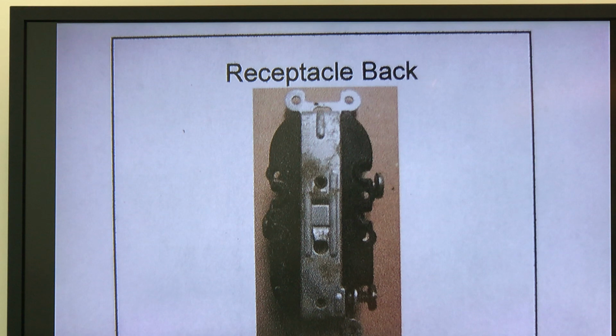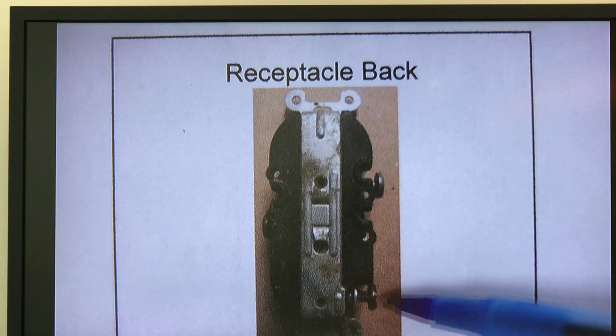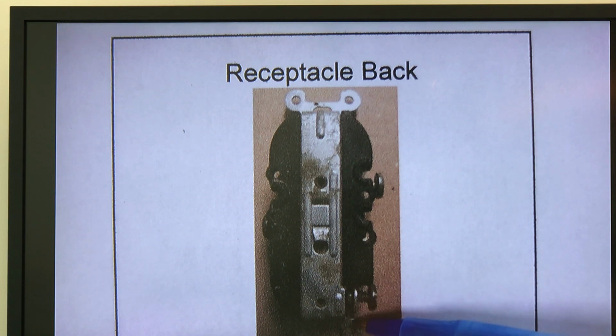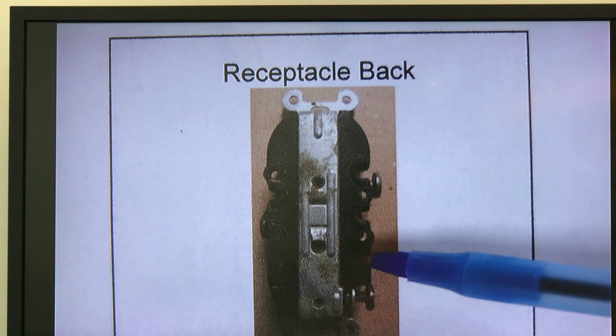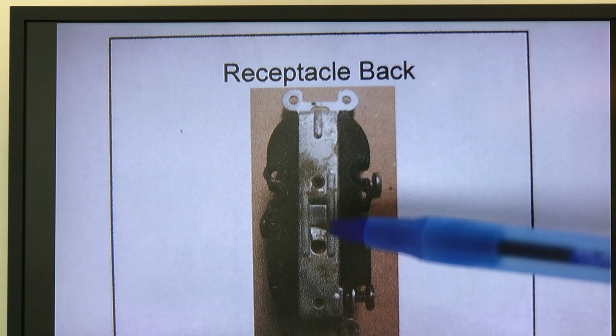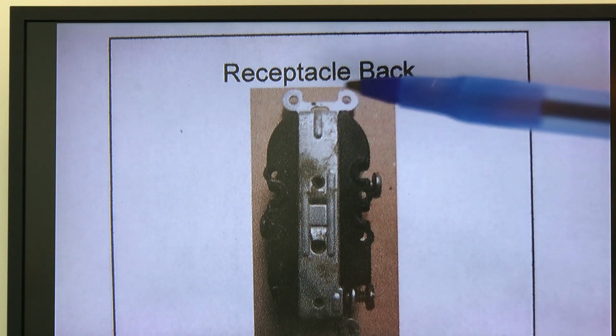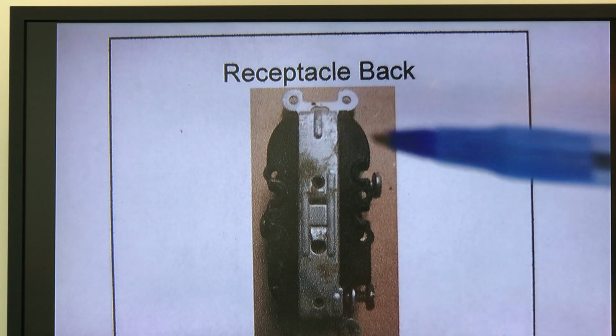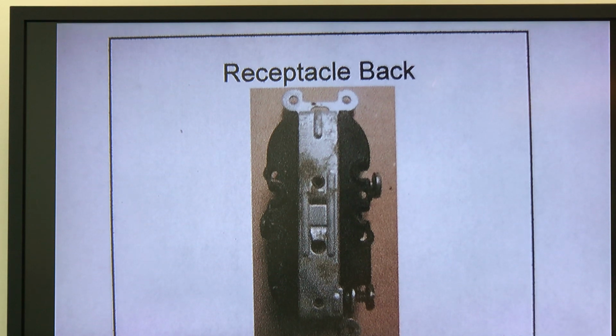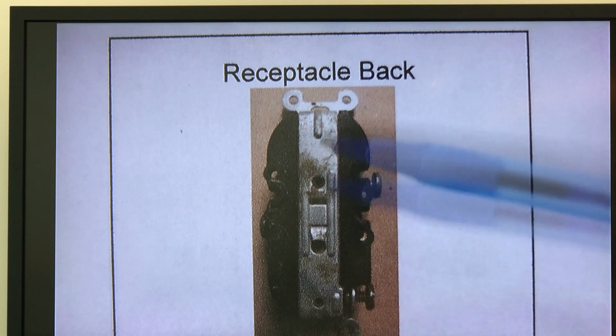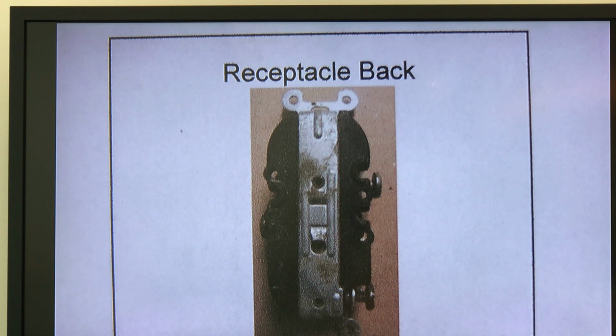If you take a look at the back of the receptacle, and this is the same device, and it was one that was pulled from service, because they do get a little grungy. You're looking at the back, and down here I want you to notice that here is a screw. That's for the ground connection. That ground connection is established to the little piece of metal here, which is actually an extension of this entire back strap. And then these little wings up in here where they attach into the electrical box. Everything that you see there that's aluminum or steel colored or tin colored if you prefer, that's a grounding connection. So that's the back of the receptacle.